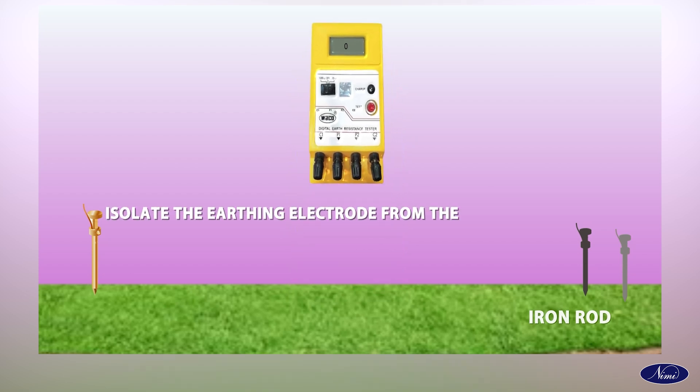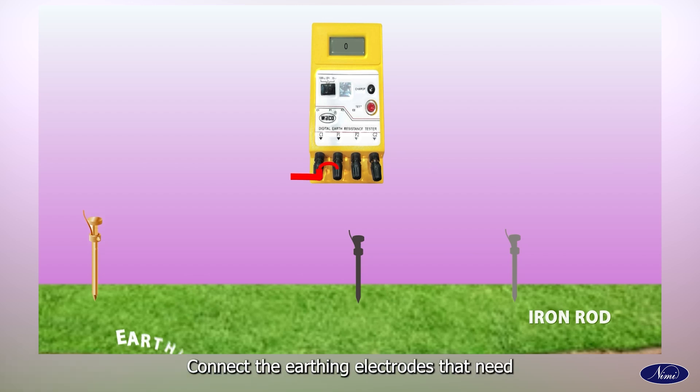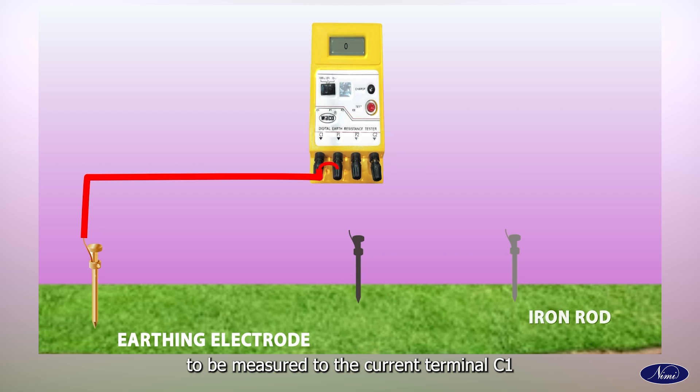Isolate the earthing electrode from the electrical system in which resistance has to be measured. Make a short between the terminals P1 and C1 with a jumper wire on the earth tester. Connect the earthing electrode that needs to be measured to the current terminal C1. Connect the other two rods with P2 and C2 terminals using insulated wires.